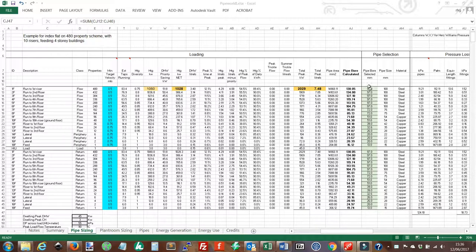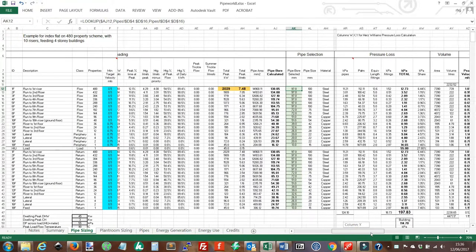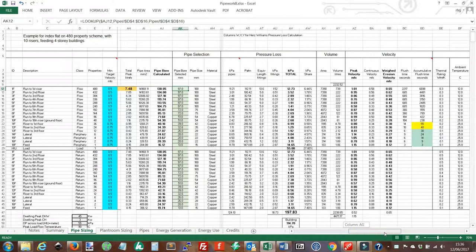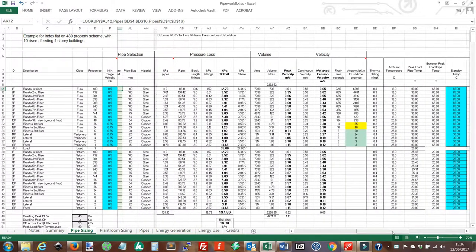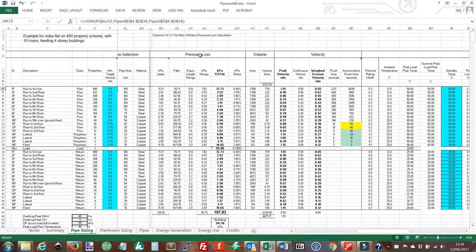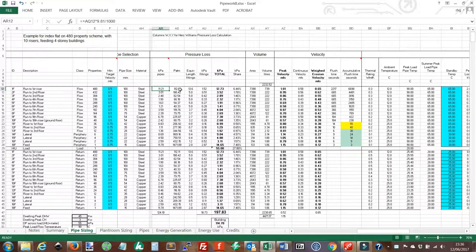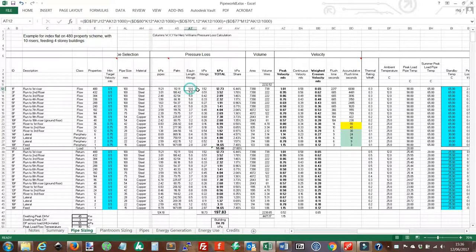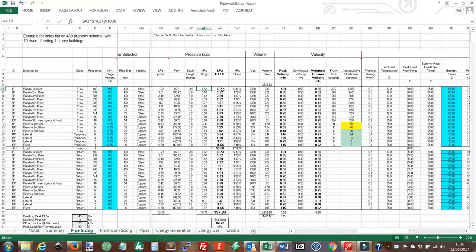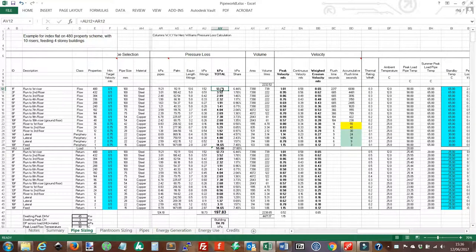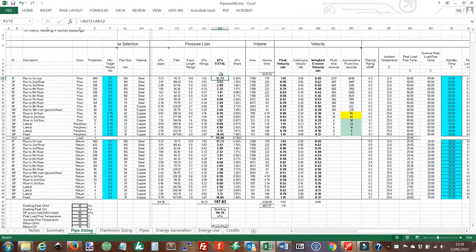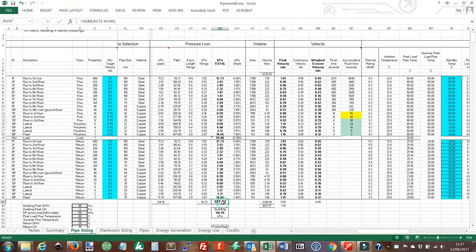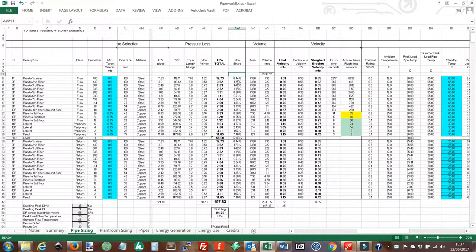Now once we have our selected pipe size, we can work out the actual figures for the heat network. So these include the pressure losses. So we're working out the pressure loss on the pipes, pascals per meter. We're adding up the fittings to get our equivalent length, press drops on the fittings. That gives us a total pressure loss on that pipe. These are totaled up across the whole site to give us our total pressure losses down here and in the building. And then we have a percentage share of the losses.